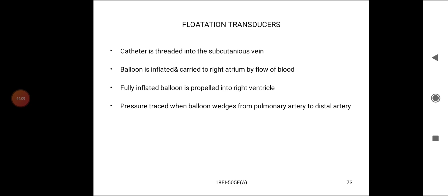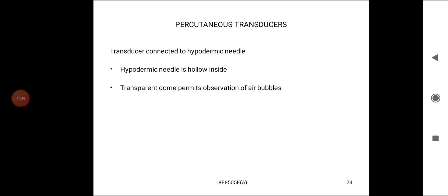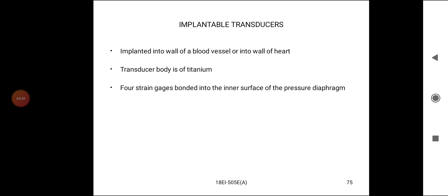Percutaneous transducer. The transducer is connected to a hypodermic needle, which is hollow inside. A transparent dome permits observation of air bubbles. Implantable transducers are implanted into the wall of a blood vessel or into the wall of the heart. The transducer body is titanium, with four strain gauges bonded to the inner surface of the pressure diaphragm.